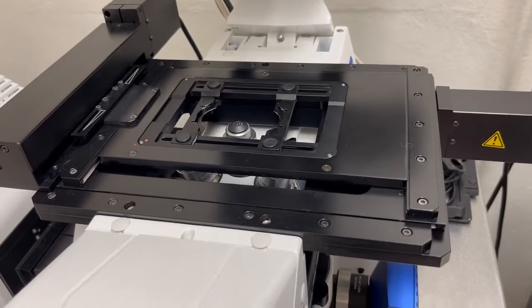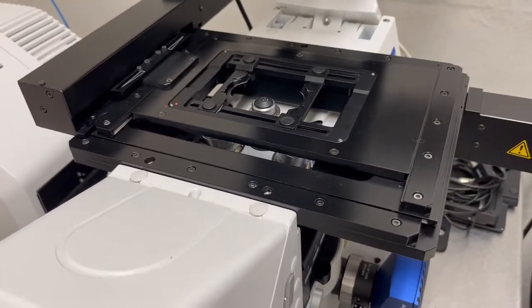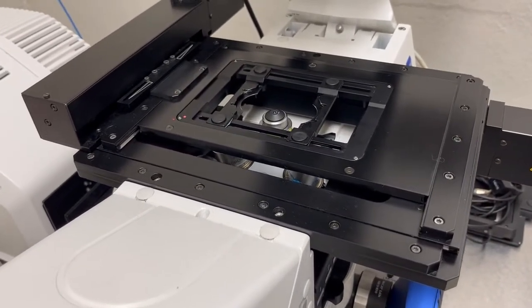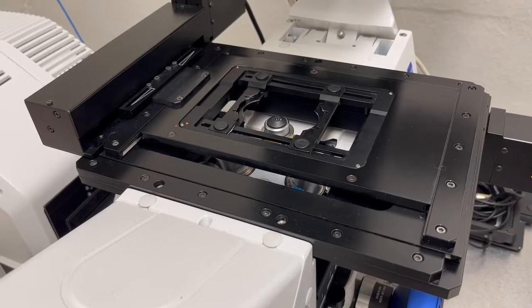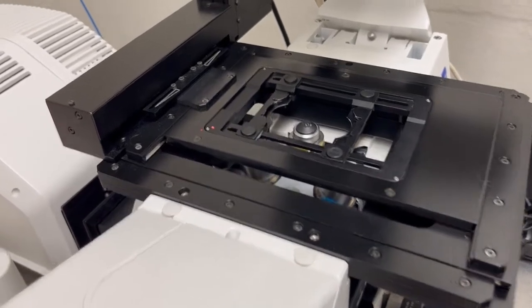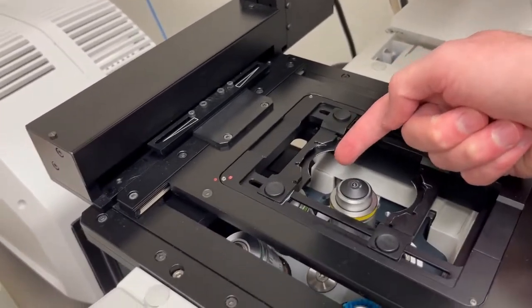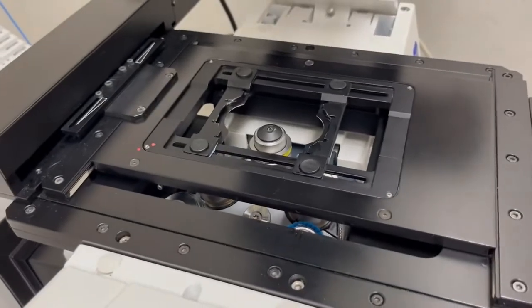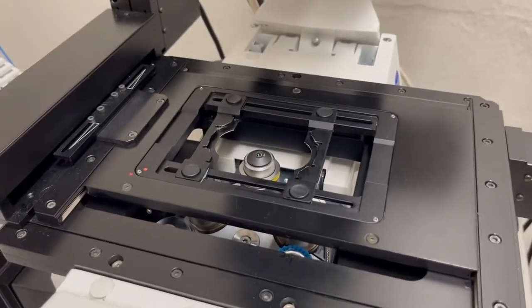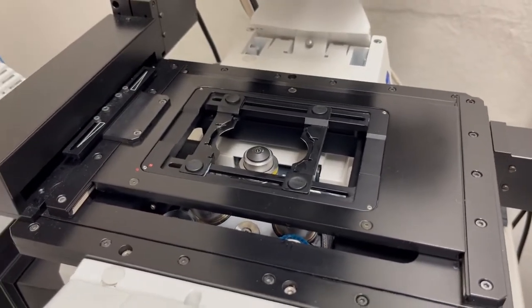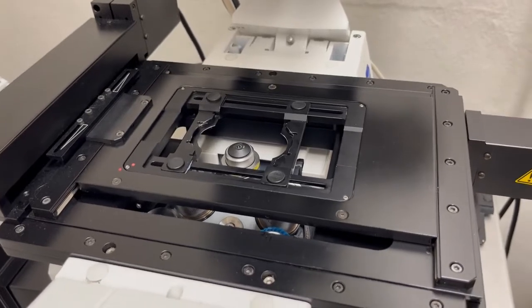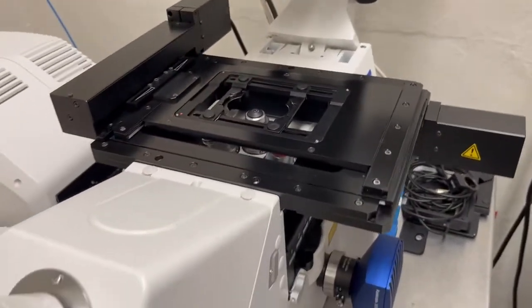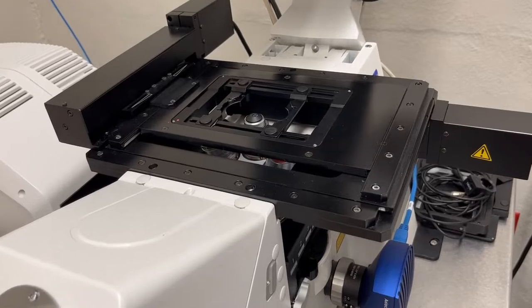I would recommend that you do not use the fast mode when you have an oil objective to avoid slamming this metal piece into the top of the oil objective and destroying $10,000 worth of expensive equipment. So that's how you move the stage. Just be careful, and you shouldn't have any problems. I'll see you next time.